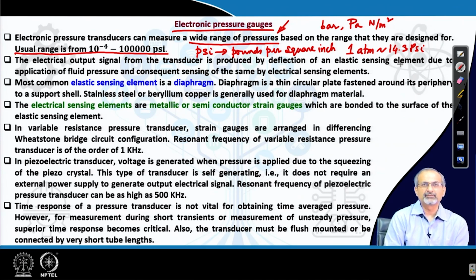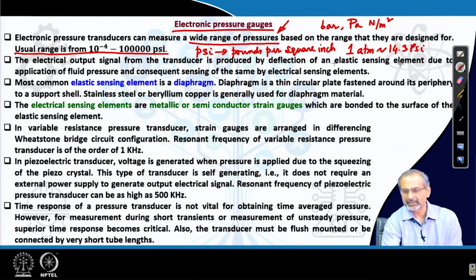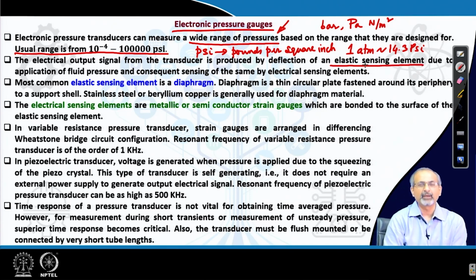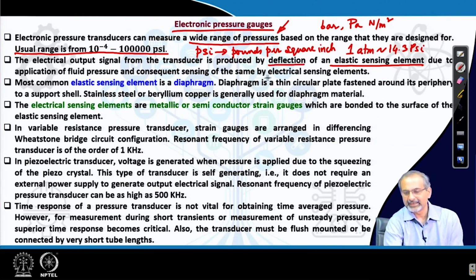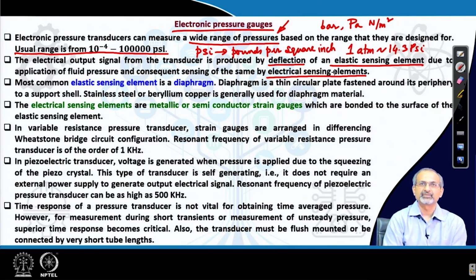The electrical output signal from the transducer is produced by deflection of an elastic sensing element due to application of fluid pressure and consequent sensing of that deflection by an electrical sensing element or elements. That means, pressure causes a deflection in an elastic sensing element, and then that is converted into an electrical signal or current using electrical sensing elements. Well, the strategy remains exactly the same as what we have discussed in the case of electronic balances as well, but the configuration is different.